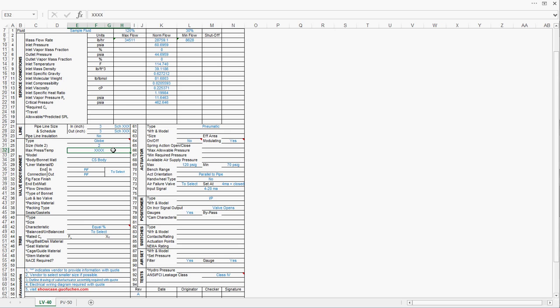Regarding the maximum pressure and temperature, you can simply take the upstream equipment design pressure and temperature. The material, carbon steel, is sufficient most of the time. However, if you have cryogenic conditions, you might want to go with stainless steel.